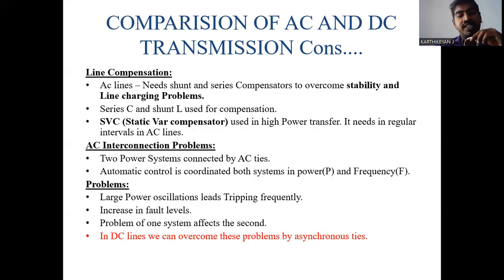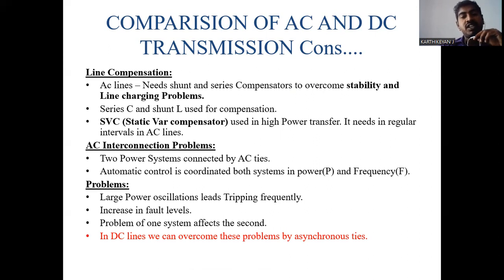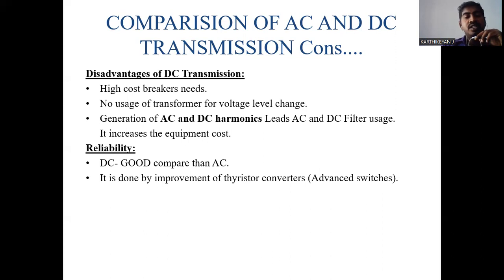Regarding line compensation, AC transmission lines require series and shunt compensators to overcome stability and line charging problems, and to compensate reactive power under varying load conditions. In DC transmission, no transmission line compensator is needed — only utility system compensation is sufficient. In terms of reliability, DC is better than AC because the DC system is more compact and secure. Using cables instead of overhead lines increases the lifespan of the transmission system.